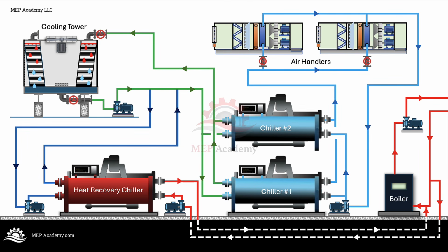A heat recovery chiller removes heat from a cooling load and delivers that heat to a heating load. It does not just make chilled water. It manages heat. And when the application is right, it can reduce boiler runtime, reduce cooling tower load, lower energy use, and improve the overall performance of the central plant.